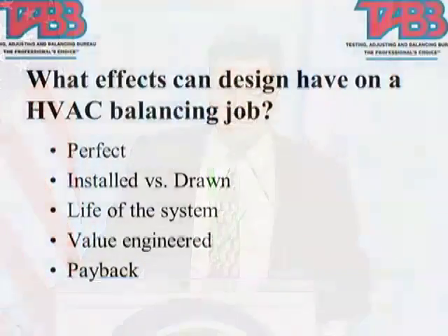And we wonder why, and to get that need of why we have balancers go out and do all this adjusting to tune these systems so we can get our energy efficiencies and our cost per square foot down on what it takes to take care of it. That's some of the limitations put on the HVAC systems. And then we have the architects as well saying you don't have enough space.